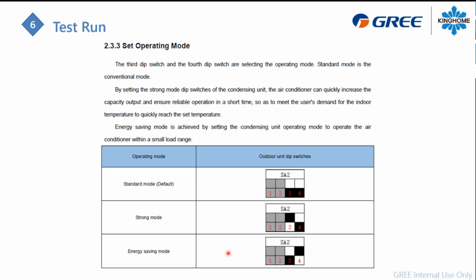At that point, you can use energy saving mode to reduce the capacity of the compressor a little bit. That will make the system run a bit longer, maybe 20, 25, 30 minutes of running time, and then you will remove more moisture and humidity from the air. Then the homeowner will be more comfortable in the house. These are tips you can use just by flipping some dip switches on the board. This is really awesome about this unit: you can configure the system as you want it to be.